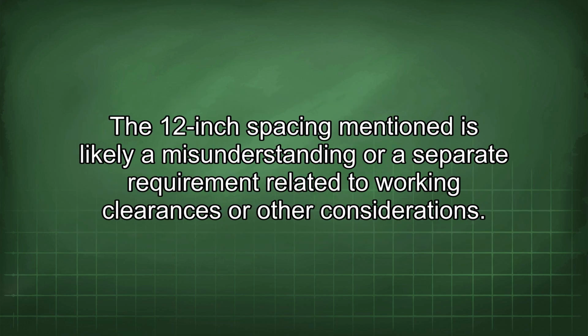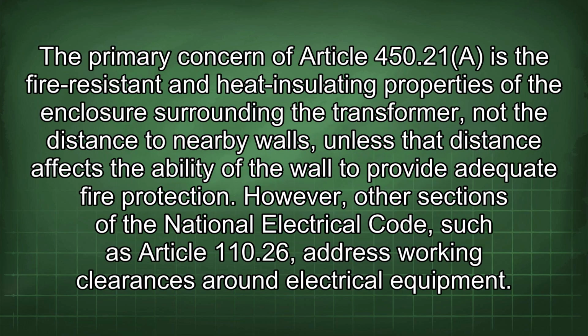The 12-inch spacing mentioned is likely a misunderstanding or a separate requirement related to working clearances or other considerations. The primary concern of Article 450.21 is the fire-resistant and heat-insulating properties of the enclosure surrounding the transformer, not the distance to nearby walls, unless the distance affects the ability of the wall to provide adequate fire protection.